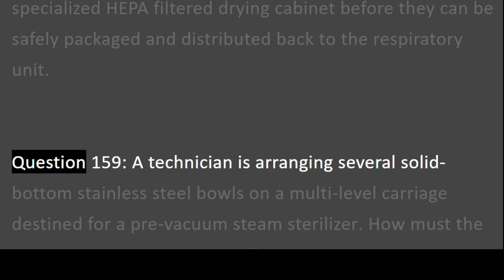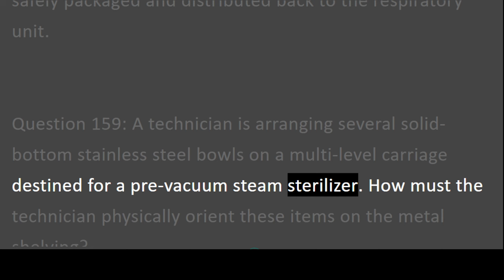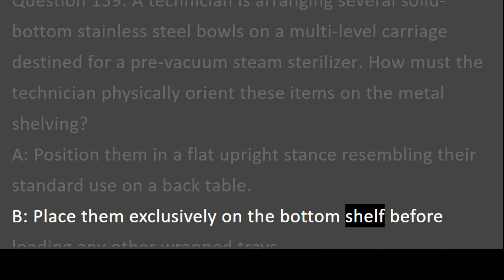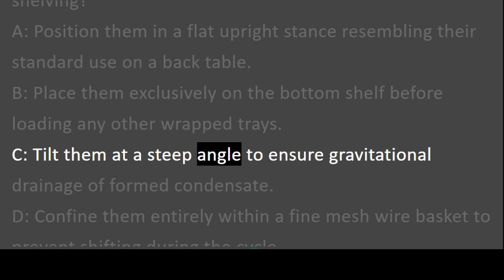Question 159. A technician is arranging several solid-bottom stainless steel bowls on a multi-level carriage destined for a pre-vacuum steam sterilizer. How must the technician physically orient these items on the metal shelving? A. Position them in a flat upright stance resembling their standard use on a back table. B. Place them exclusively on the bottom shelf before loading any other wrapped trays. C. Tilt them at a steep angle to ensure gravitational drainage of formed condensate. D. Confine them entirely within a fine mesh wire basket to prevent shifting during the cycle.